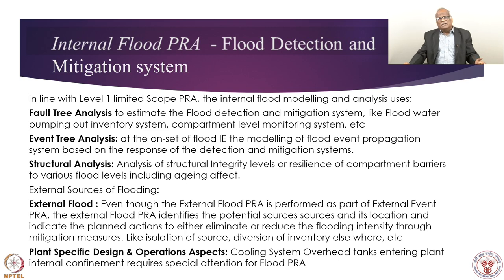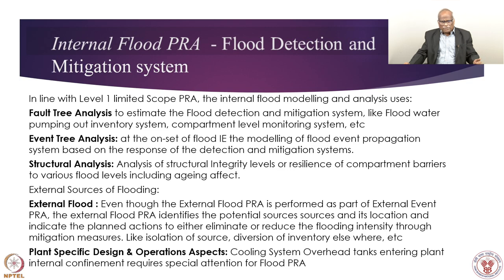Most procedural points are in line with level 1 PRA discussed in previous lectures. Fault tree and event tree analysis apply here; the new element is structural analysis. Unlike seismic events, for flood we create barriers: the plant must ensure these barriers resist flood levels and keep compartment definitions intact — this relates to the civil component of the plant. Externally, how external flood affects internal events — any leakage from a boundary where an external source contributes to internal sources and becomes an initiating event must be considered.